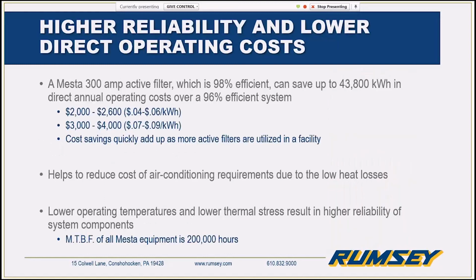And with that efficiency comes direct operating cost savings for the customer. So we have a good little example here with a 300 amp unit, ours being 98%, the next closest guy out there being 96%, running max load all year round. There's a little calculator to say, what's my cost per kilowatt hour? Some of you may be familiar with what you have, but you could be saving from $2,000 to $4,000 if you fall within that band. We know some of our customers actually have higher costs than that, and you can see that add up a lot when you have multiple filters in the facility.